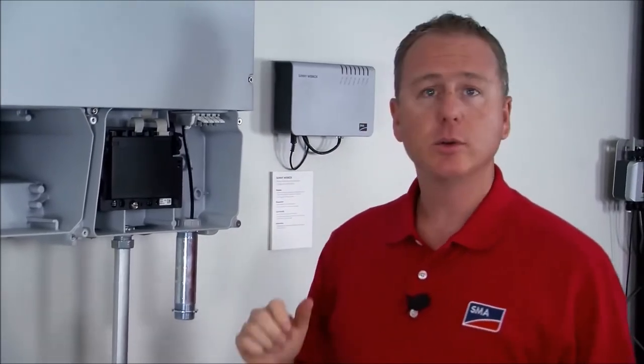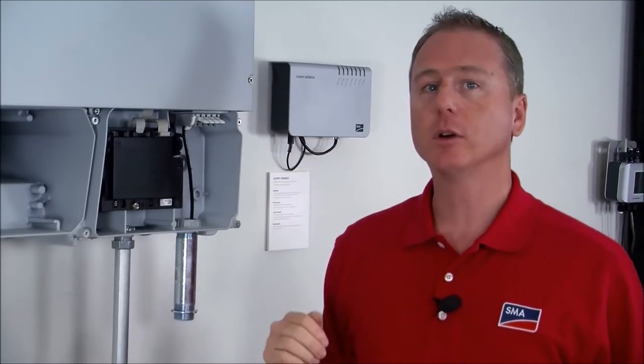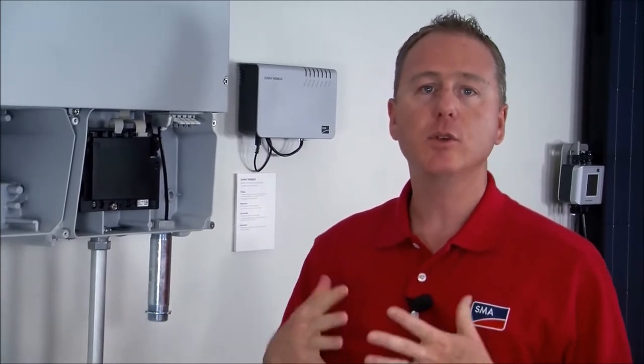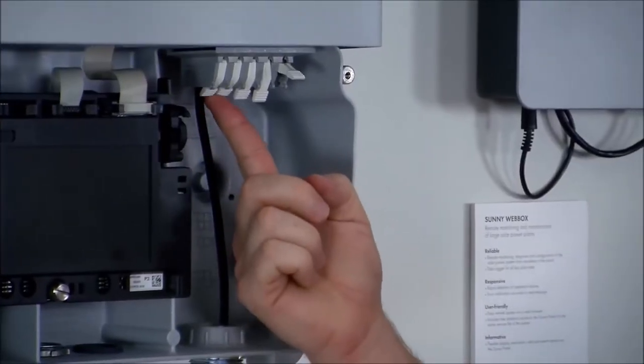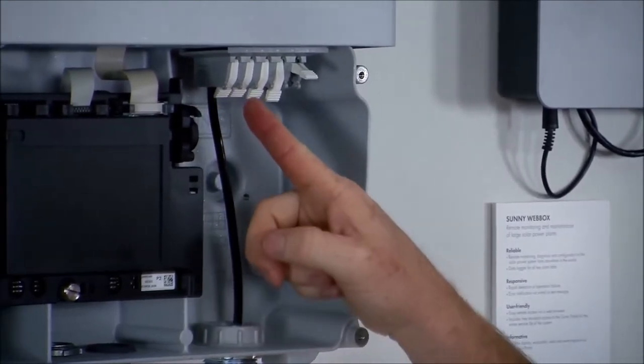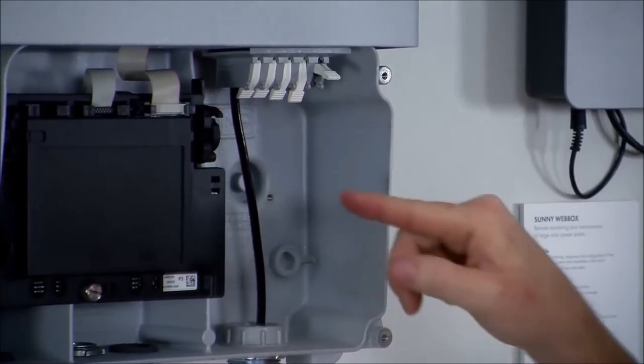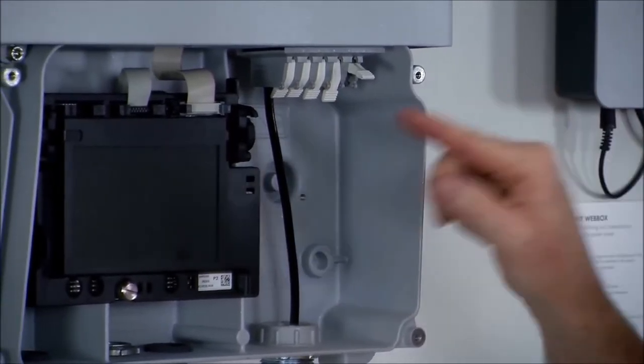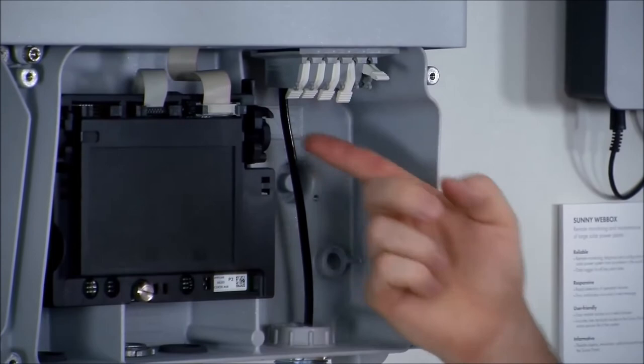Now what I'm going to do is show you what the levers look like when they're not fully open or fully closed and this is going to cause problems on the installation if you don't follow the instructions on how to securely clamp these things down. So the L1 and L2 conductors are fully shut but you can see the L3 is not quite down nor is the neutral. So be very careful when you do the installation that you always make sure the conductors are all the way down.